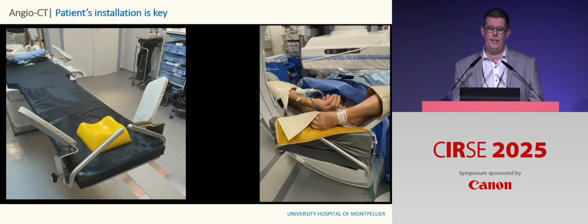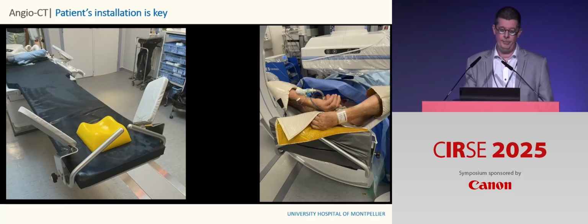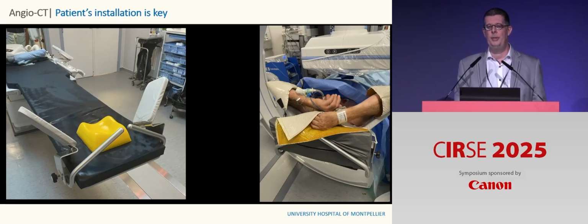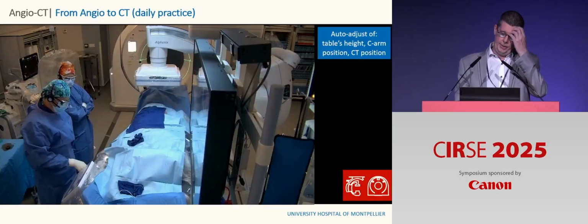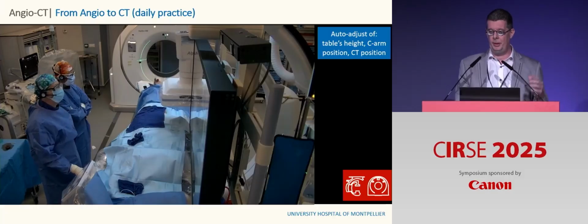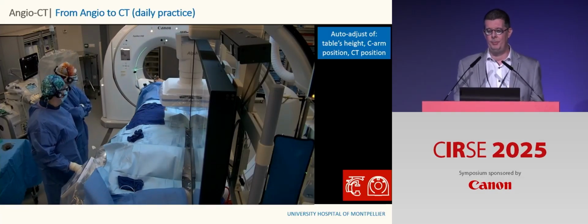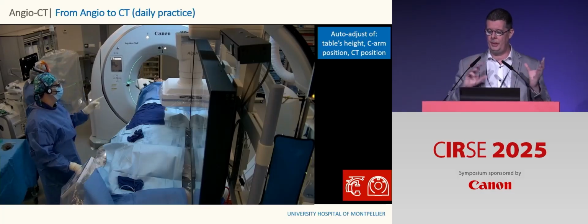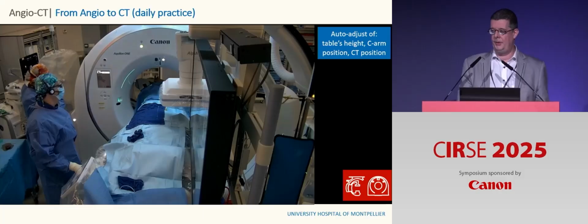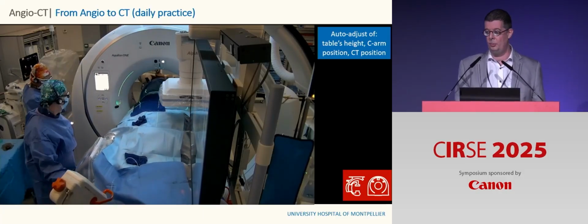But before diving into clinical cases, first things first, patient installation is key. We are using such a dedicated system on the table to maintain the patient's arm above the head safely, without any risk of stretch or neurological injury. This is a crucial detail because we make sure that we can use CT in every circumstance safely and with the best possible image quality. Now, we can see how it works in practice on the patient. The switch between angio and CT is now extremely simple. Again, only one button to press, and everything works together. And as you can see, it's much, much faster than any cone beam CT system.